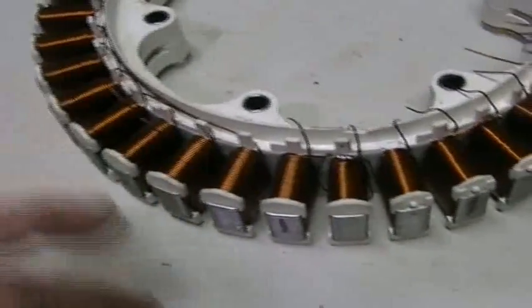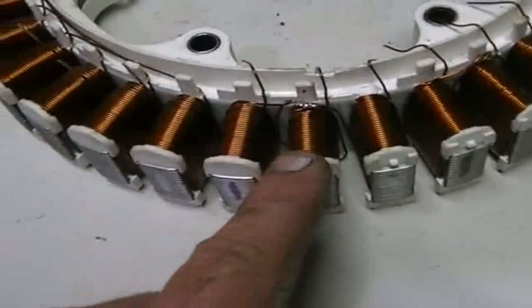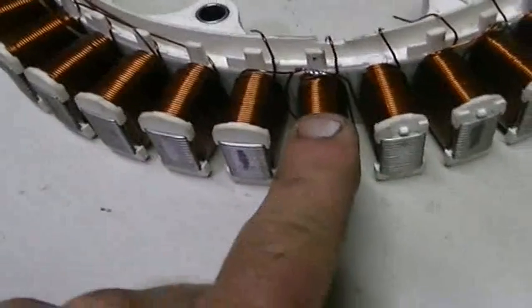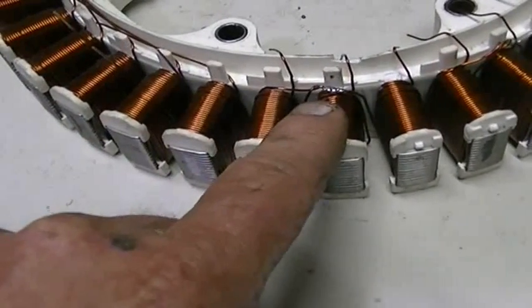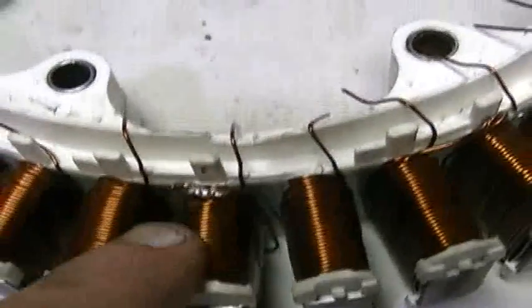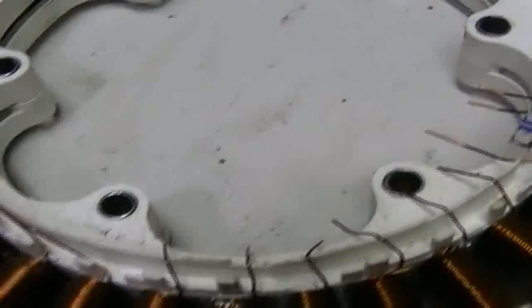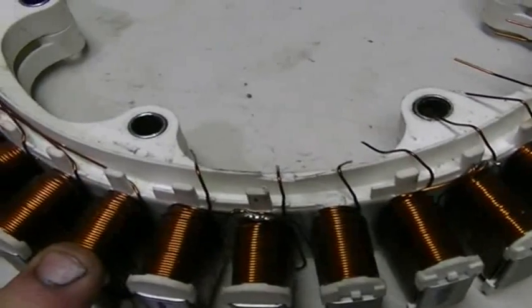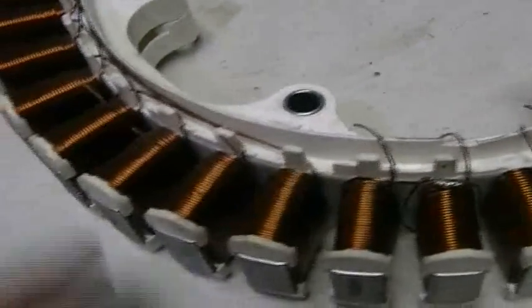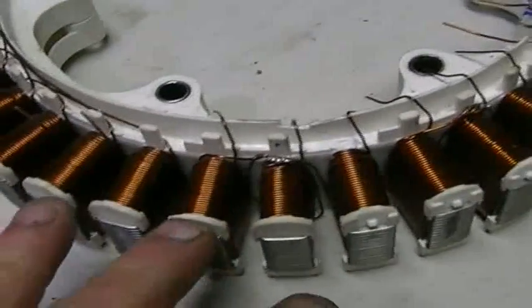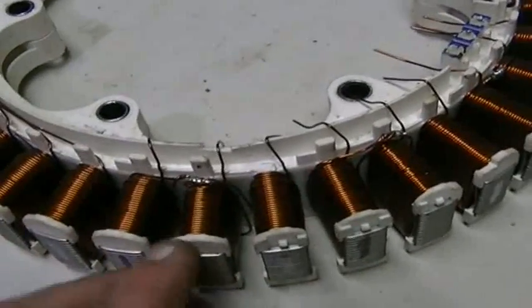What we have to do is cut all the wires. We take first three coils, so that's one phase, two phase, three phase, and we join the ends. Each end of each coil is all joined together like these ones here. Then the start of each coil you just fold over the edge. We have to parallel connect each coil on each phase. It's star configuration.